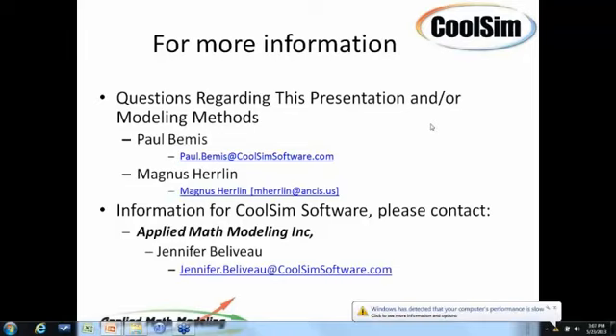Whichever you want. Just the additional comment was that liquid could also mean liquid rack doors. Yeah, I mentioned liquid rack doors. I see those. Those are popular. As Magnus pointed out, when you've got a liquid door in place, what I would do is model the delta T across it as being different, or the load in it as being different, but there still is air coming out into the room, just at a different temperature, and leave the rest of it, unless there are doors on all the equipment.